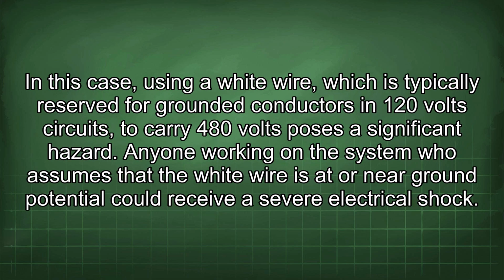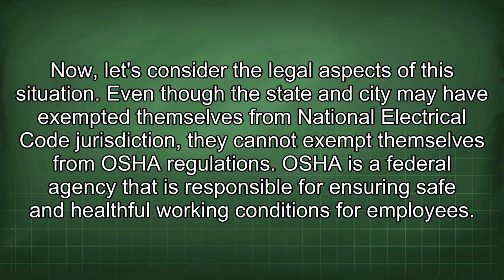In this case, using a white wire, which is typically reserved for grounded conductors in 120-volt circuits, to carry 480 volts poses a significant hazard. Anyone working on the system who assumes that the white wire is at or near ground potential could receive a severe electrical shock. Now, let's consider the legal aspects of this situation. Even though the state and city may have exempted themselves from National Electrical Code jurisdiction, they cannot exempt themselves from OSHA regulations.